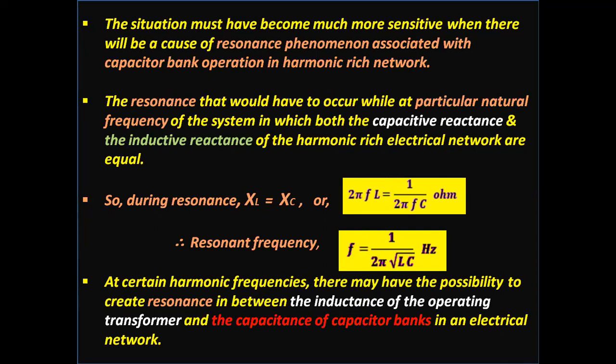The situation becomes much more sensitive when there is a resonance phenomenon associated with capacitor bank operation in a harmonic-rich network. Resonance occurs at the particular natural frequency of the system at which both the capacitive reactance and the inductive reactance of the harmonic-rich electrical network are equal — that is XL = XC — or resonance frequency f = 1/(2π√LC) hertz.